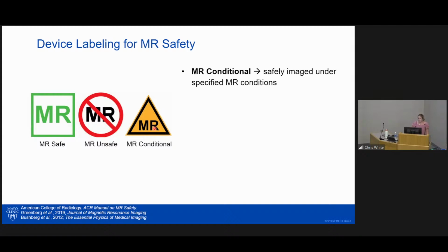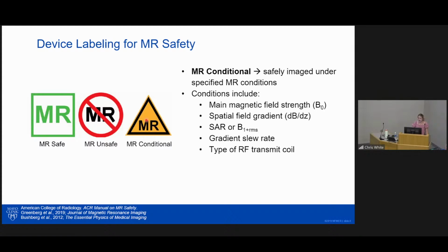So commonly imposed conditions for the device include a maximum main magnetic field strength, or B0 field, which we talked about, maximum spatial field gradient, dB/dz, which is how fast the B0 field changes along the direction of the scanner, maximum SAR or B1+ RMS, and I'm going to describe SAR in a little bit more detail later, and then maximum gradient slew rate and the type of RF transmit coil.